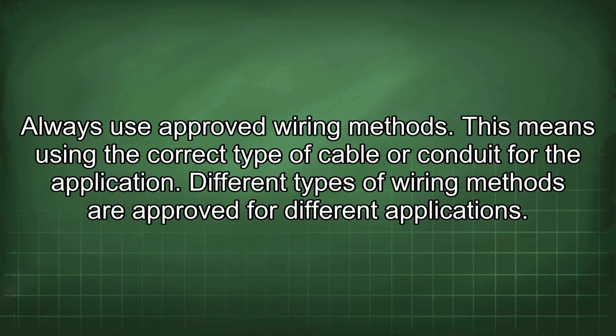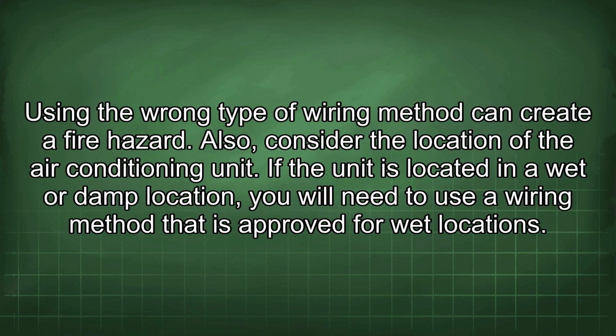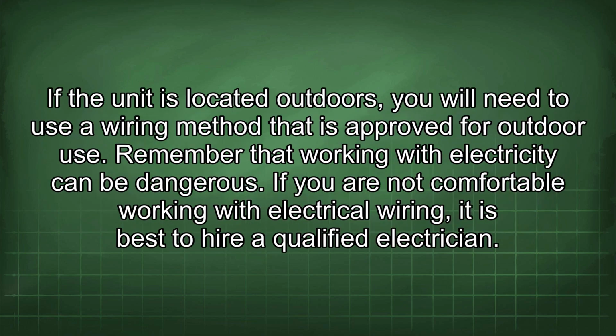Always use approved wiring methods. This means using the correct type of cable or conduit for the application. Different types of wiring methods are approved for different applications. Using the wrong type of wiring method can create a fire hazard. Also, consider the location of the air conditioning unit. If the unit is located in a wet or damp location, you will need to use a wiring method that is approved for wet locations. If the unit is located outdoors, you will need to use a wiring method that is approved for outdoor use.